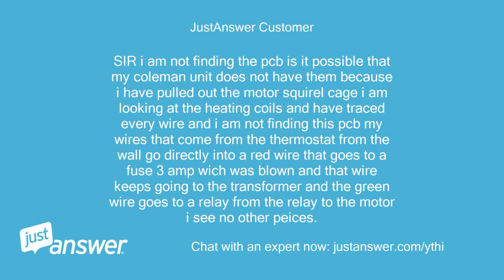Sir, I am not finding the PCB. Is it possible that my Coleman unit does not have them because I have pulled out the motor squirrel cage? I am looking at the heating coils and have traced every wire, and I am not finding this PCB. My wires that come from the thermostat from the wall go directly into a red wire that goes to a 3 amp fuse which was blown, and that wire keeps going to the transformer, and the green wire goes to a relay, from the relay to the motor. I see no other pieces.